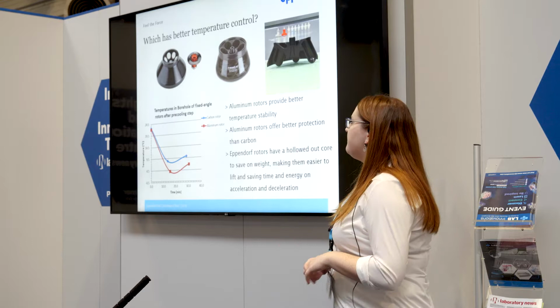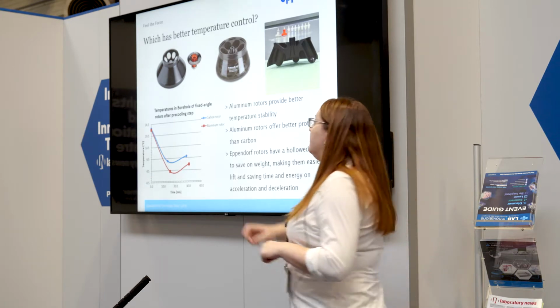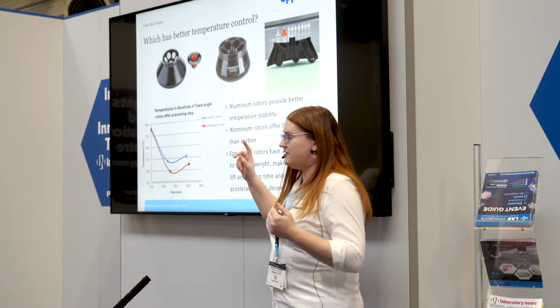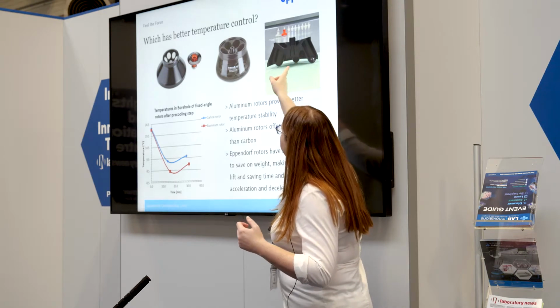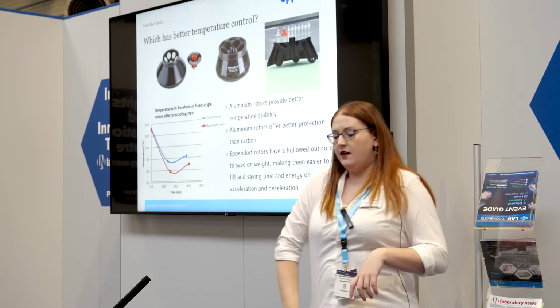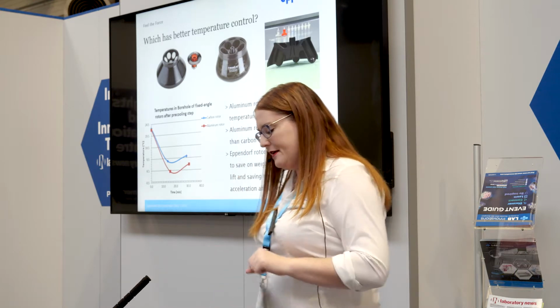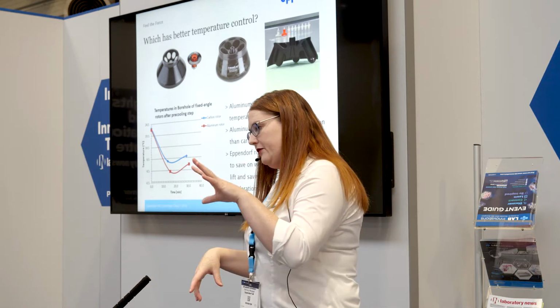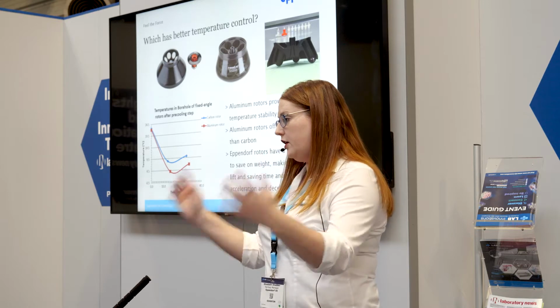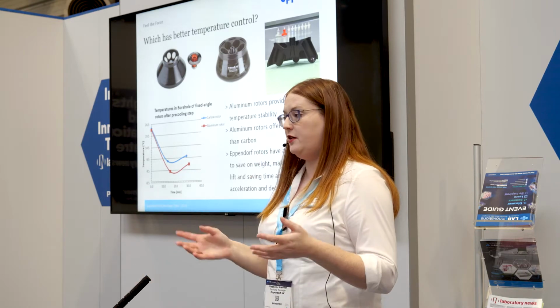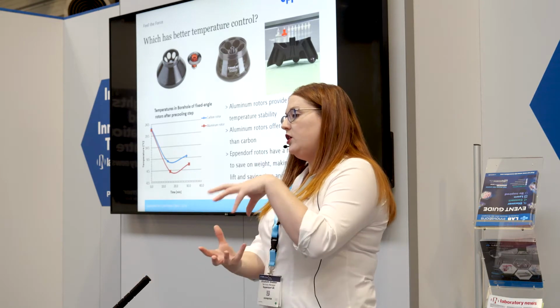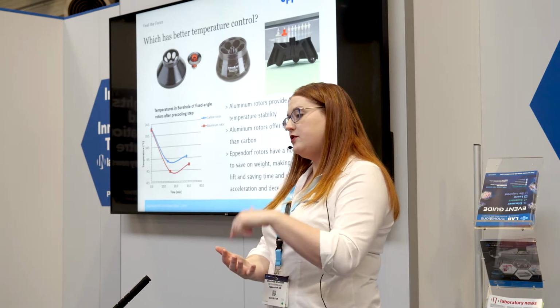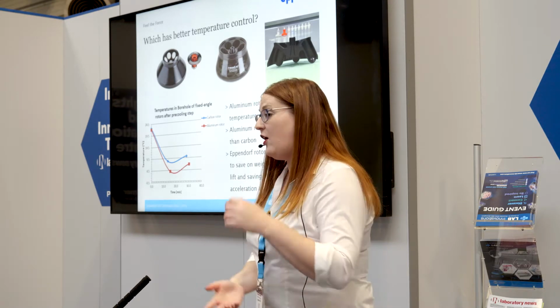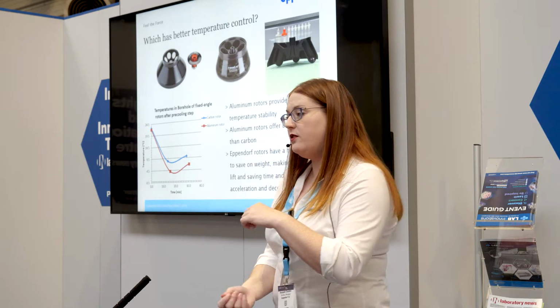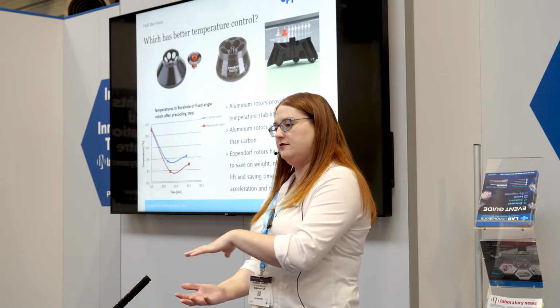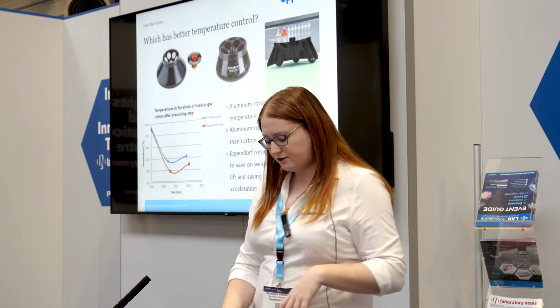One of the downsides of aluminium rotors is that they tend to be quite heavy because they're metal. So the Eppendorf ones are hollow between the boreholes to counteract this. And it's not in this presentation, but we have a great image where we've literally put a carbon fibre rotor and an aluminium rotor in a cold room for 15 minutes and then taken a picture with an infrared camera. When you look into the carbon fibre rotor, the centre of the boreholes where your sample is, it's still room temperature, whereas the whole aluminium rotor is cooled down. Okay?